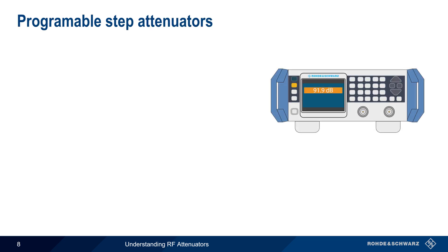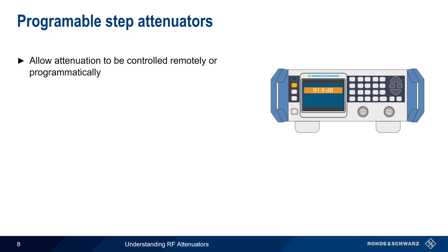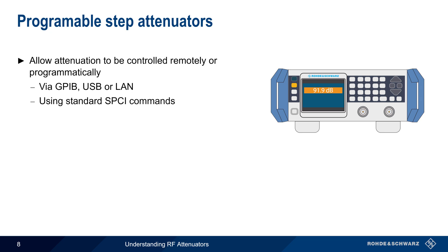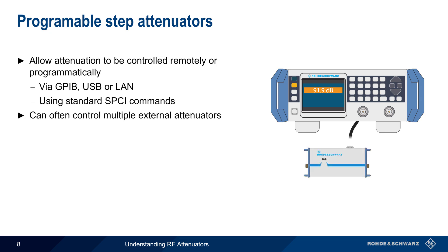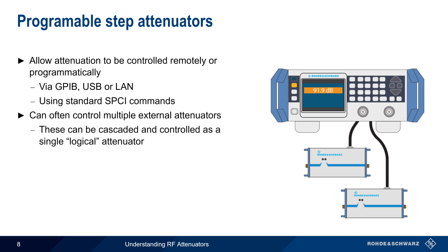Programmable step attenuators are a more sophisticated type of step attenuator, and allow for attenuation to be controlled both manually as well as programmatically or remotely via GPIB, USB, or LAN connections, and by means of industry standard SCPI commands. Many can also control one or more external attenuators, which can be cascaded and controlled as one logical attenuator.